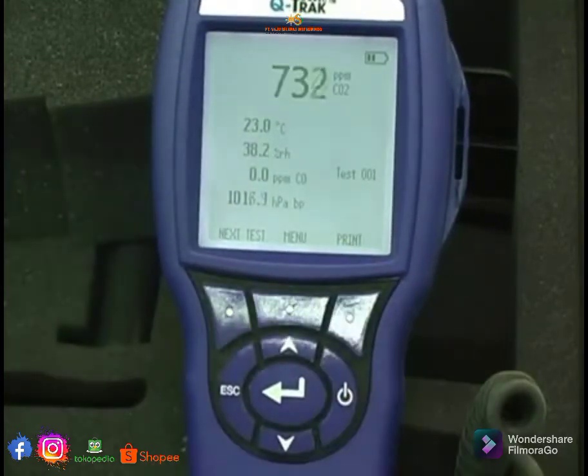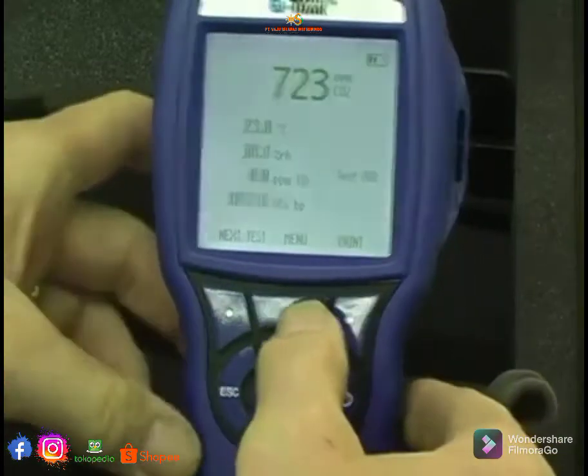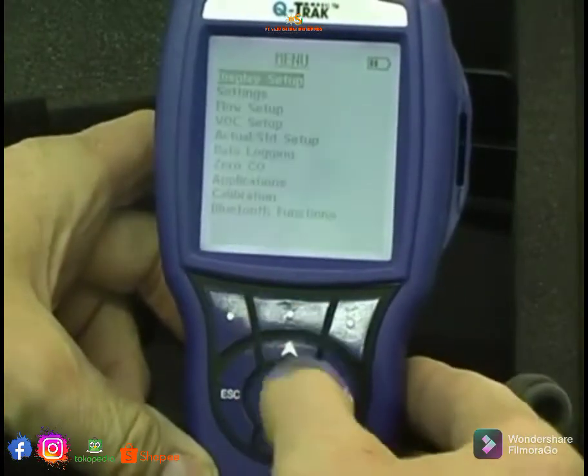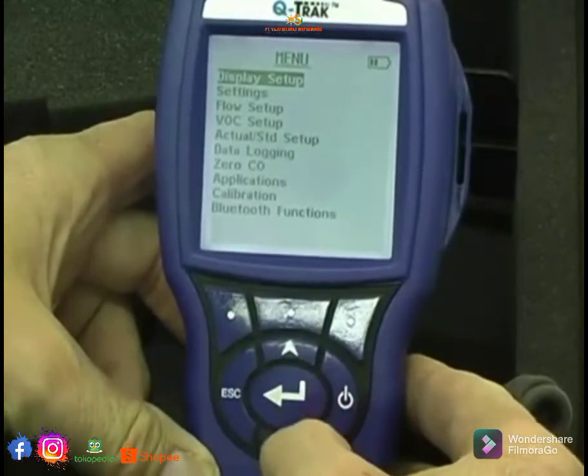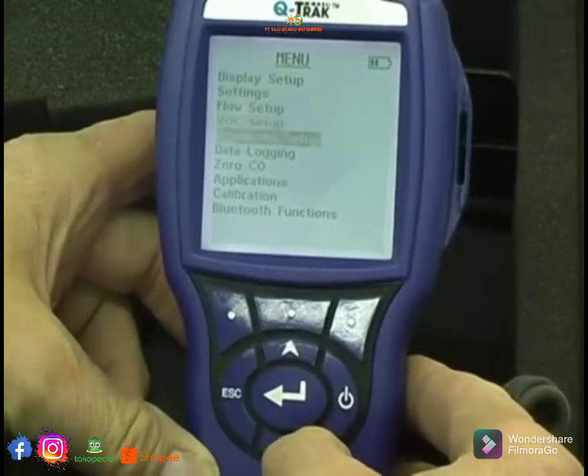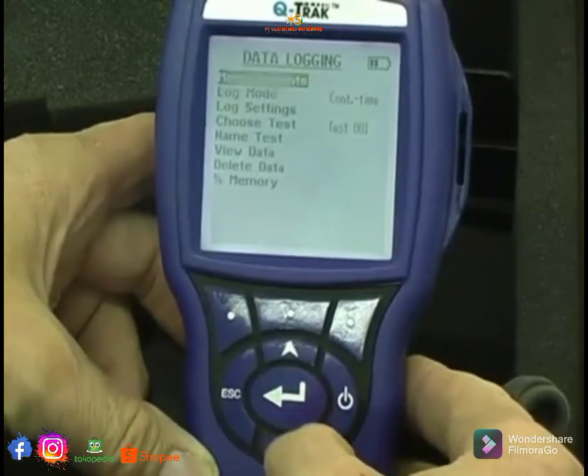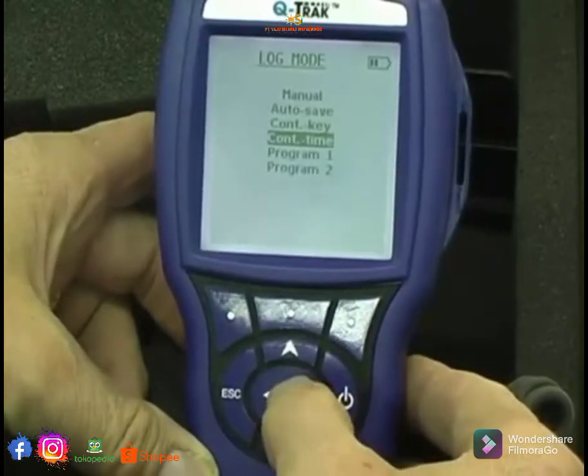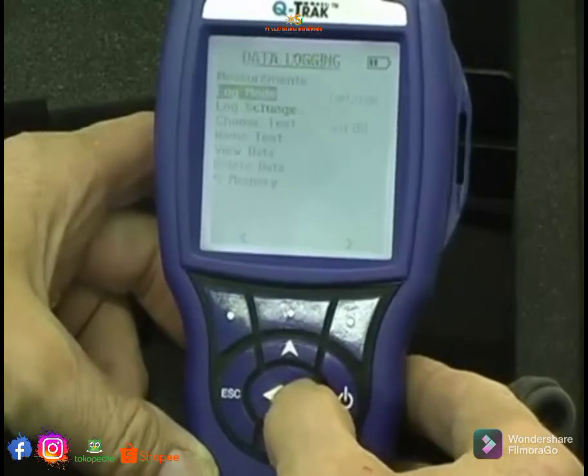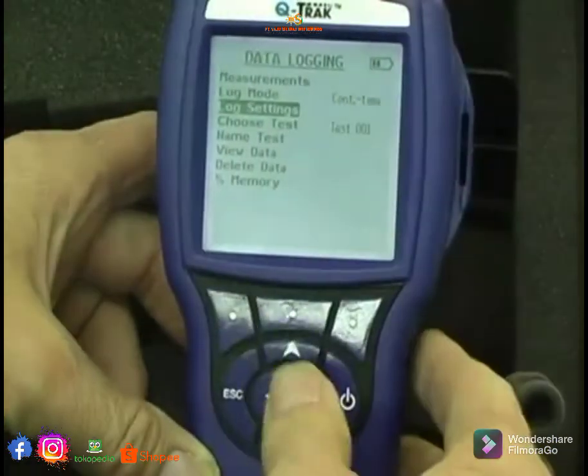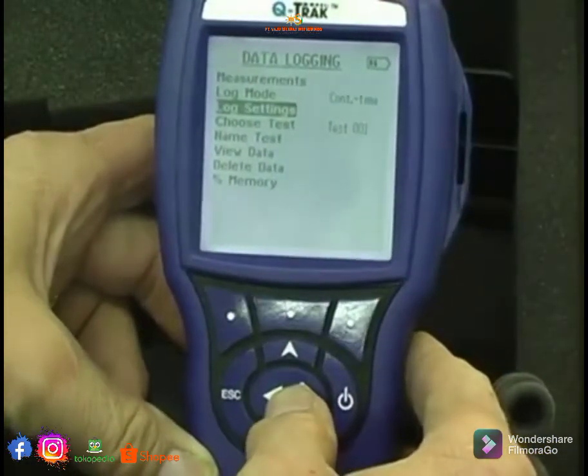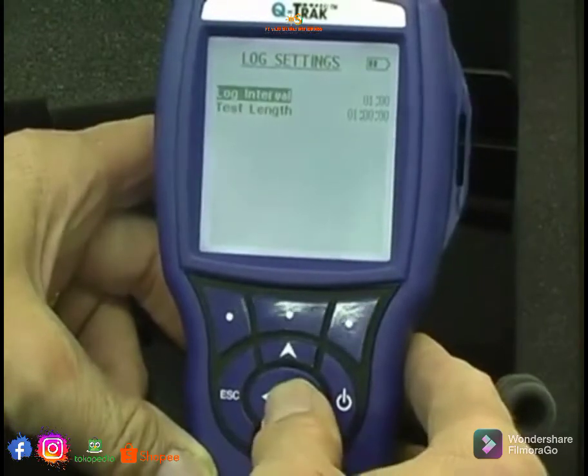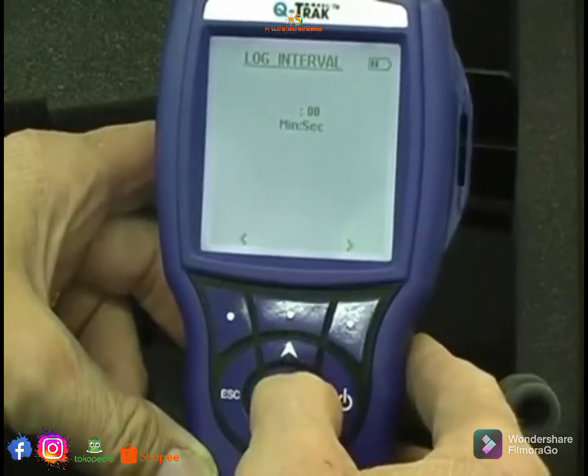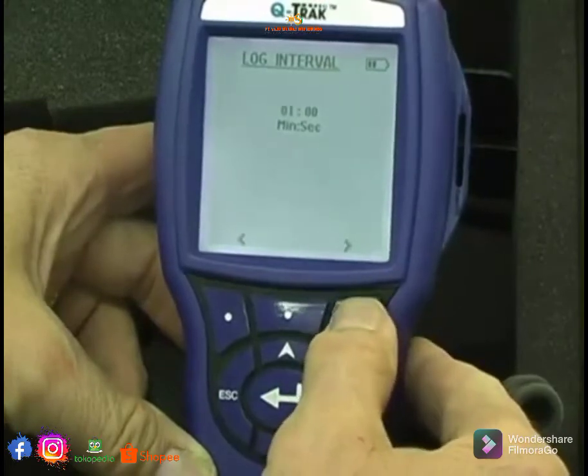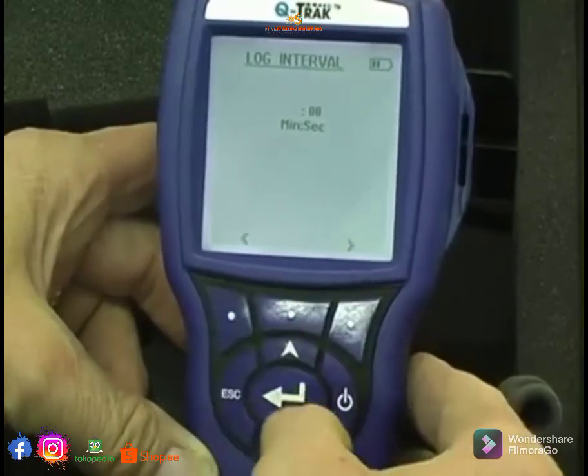Now in order to get the data logging going on this, it's simply a matter of hitting the menu key here, coming down to the data logging. I'm using the down arrow, there's data logging here. Now the log mode we select is continuous time, so it will log continuously on a time basis. Now the logger settings are set here. The time interval at the moment is set to every minute, it'll take a reading. We can jump from one field to the next by using these function keys and changing the value.